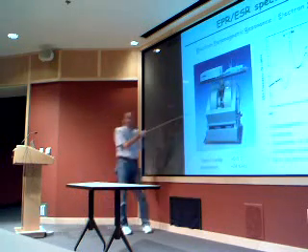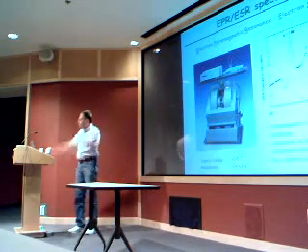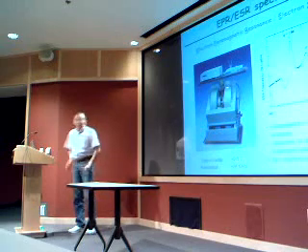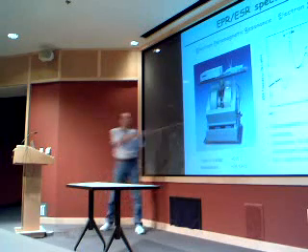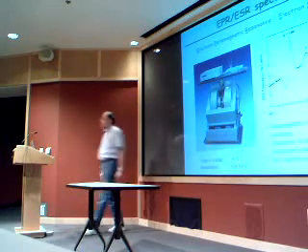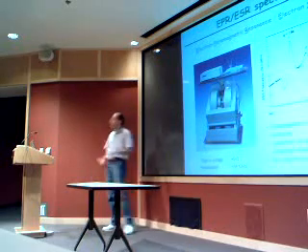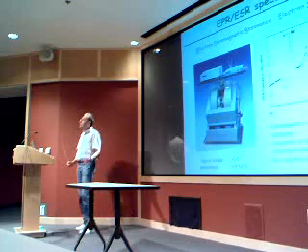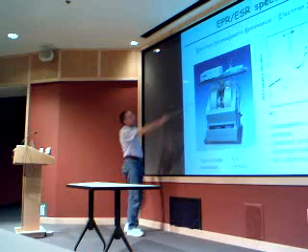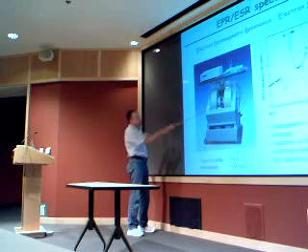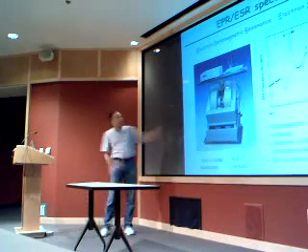So part one. This is an EPR device. It is much smaller than the one used in NMR. I think it's basically the size of this podium, and you don't need very strong magnetic fields in this case, so you can simply use some electromagnets. In the case of NMR, instead, you have to go from 10 to 20 Tesla, so you need a cryomagnet, so you need liquid helium to cool down your magnets. So this is a very convenient device, and basically the sample goes here in the middle between the expansions of the two magnets, and the principle is the same.